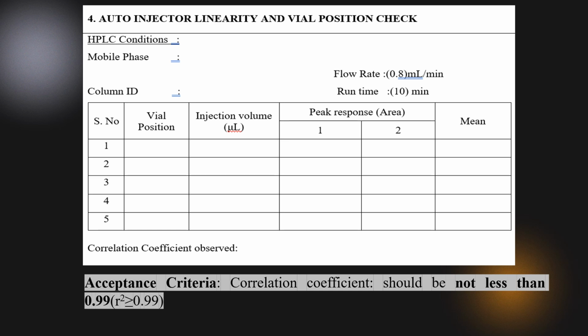Now the fourth part that needs to be calibrated in HPLC is your auto injector linearity and vial position. So what you're seeing here is that when you change the injector capacity that needs to be injected, that is, first it was 2 µL, then it was 5 µL, then it was 10 ml. So you're checking that whatever injection volume you have given, it is accurate. When you're giving the command that 5 µL of the sample needs to be injected, the system is taking that 5 µL. So how you're going to calibrate it?